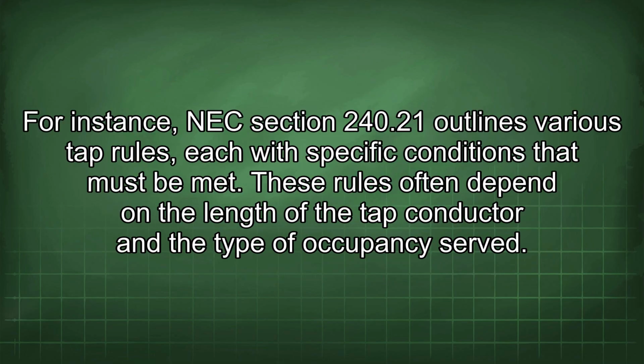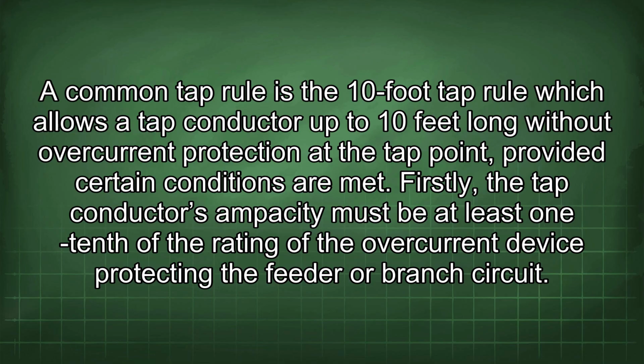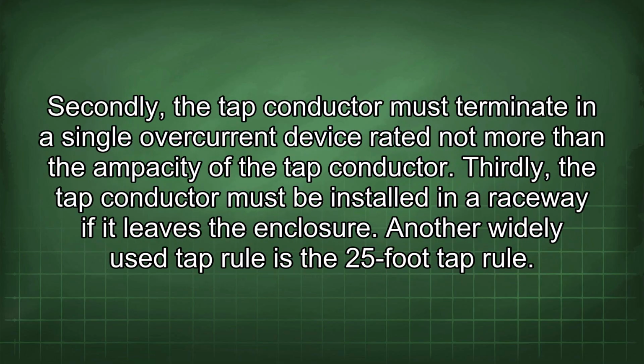For instance, NEC Section 240.21 outlines various tap rules, each with specific conditions that must be met. These rules often depend on the length of the tap conductor and the type of occupancy served. A common tap rule is the 10-foot tap rule, which allows a tap conductor up to 10 feet long without overcurrent protection at the tap point, provided certain conditions are met. Firstly, the tap conductor's ampacity must be at least 1/10 of the rating of the overcurrent device protecting the feeder or branch circuit. Secondly, the tap conductor must terminate in a single overcurrent device rated not more than the ampacity of the tap conductor. Thirdly, the tap conductor must be installed in a raceway if it leaves the enclosure.